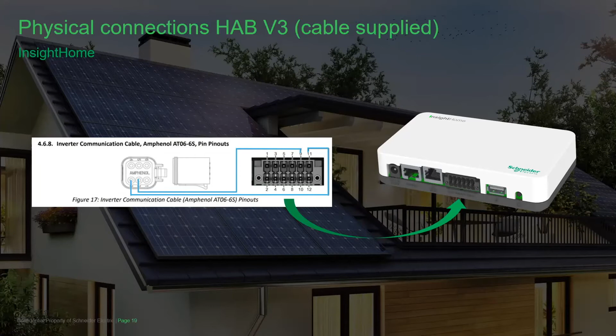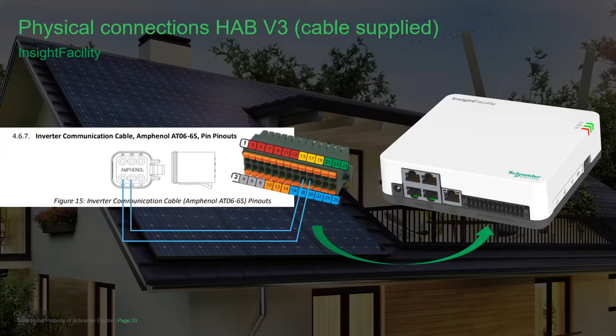If you're using Insight Facility, it has a different connector with two different RS-485 ports. Looking at RS-485 port number 1 here, you would connect pin 2 to pin 18 and pin 3 to pin 20.